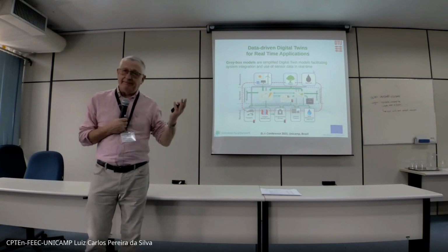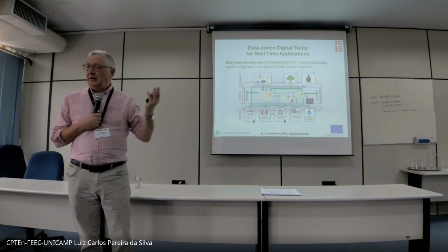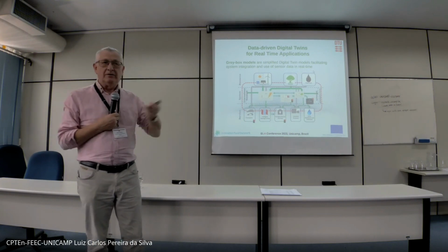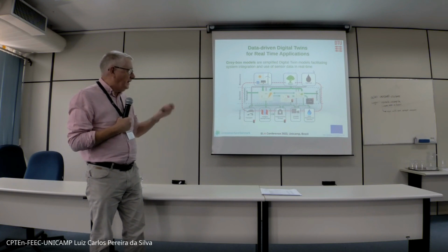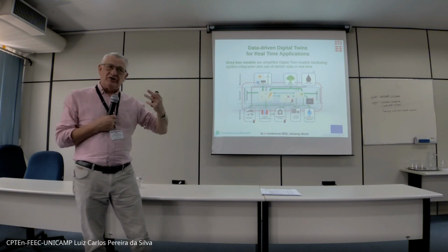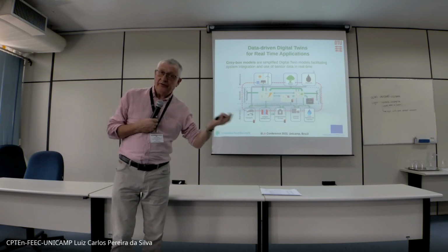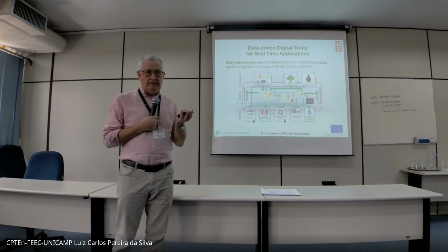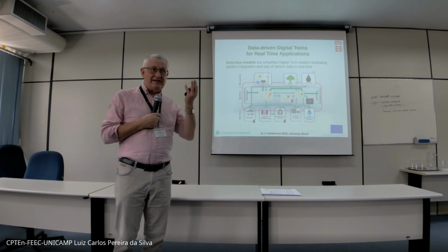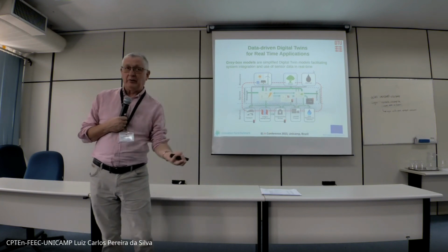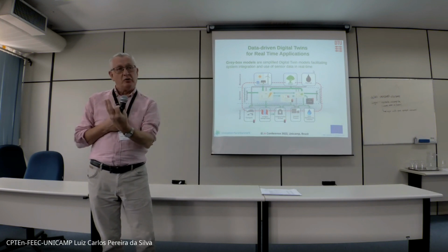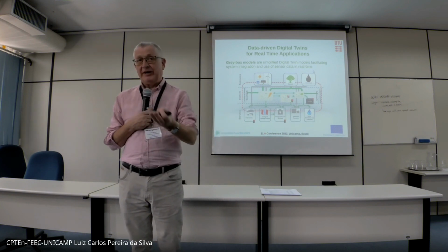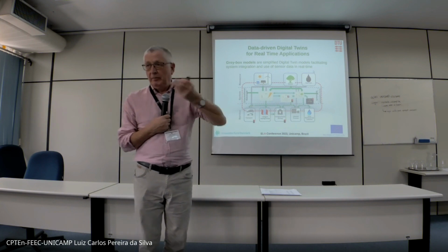So typically they are simplified models, for instance, of a building. It could be a model with 3 or 4 stages, or 2 stages, 2 RC coupled models. They are simplified models, but the models take into account both the dynamics, of course, but also the uncertainties. So the models we are using are stochastic differential equations typically, which implies that it's okay then to reduce the number of differential equations and then compensate for that by introducing what we call the diffusion term in the stochastic differential equation. Then we describe all the dynamics and stochastics with just a few parameters.